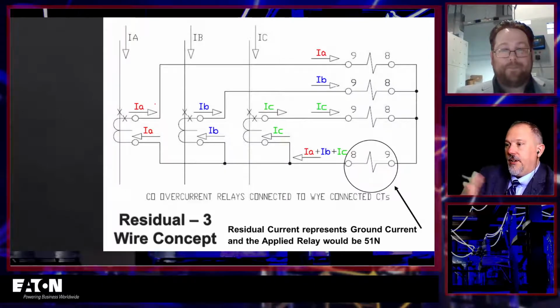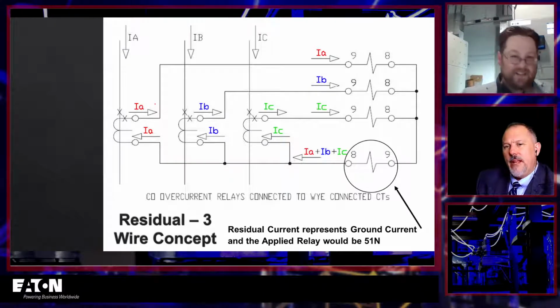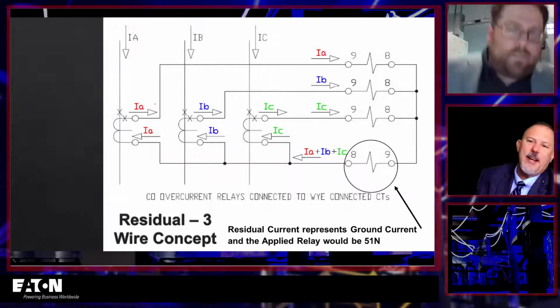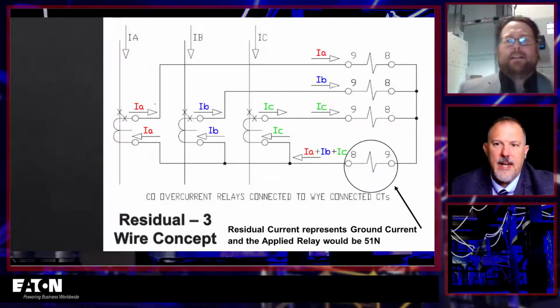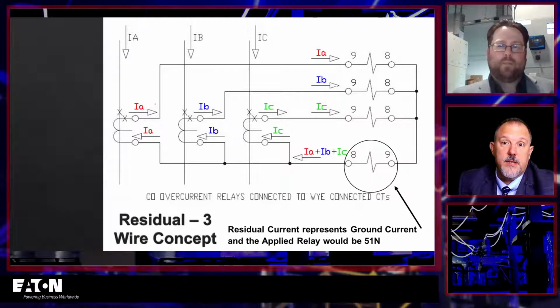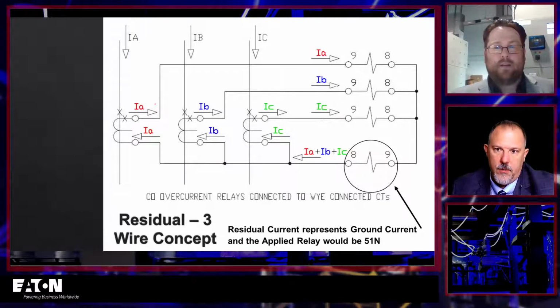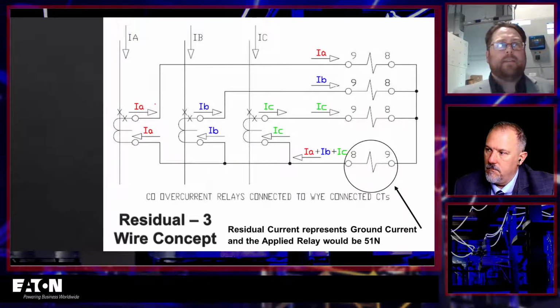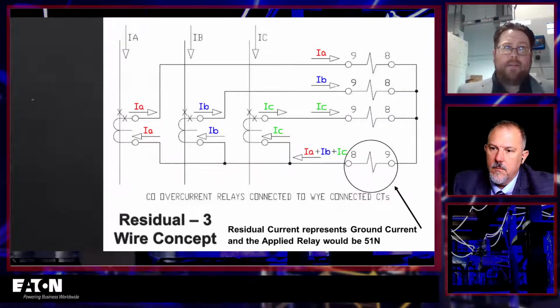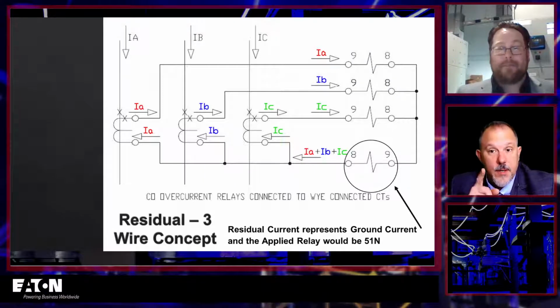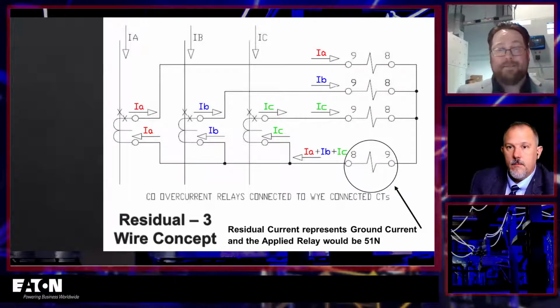And then this is again your residual concept. So your CO relays can now a CO relay. Now you're talking relays, which really would be in a medium voltage type of application, right? I've seen some relays at 480 volt lineups of switchgear, but that's a pretty sophisticated system. You might see that in a heavy industrial, but you're not going to see that in a commercial building, though. No, not typically, but it's a good note to say this doesn't just apply to the low voltage system. What we're talking about with the ground fault protection applies across the board.